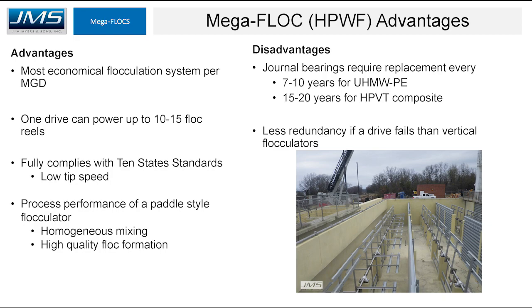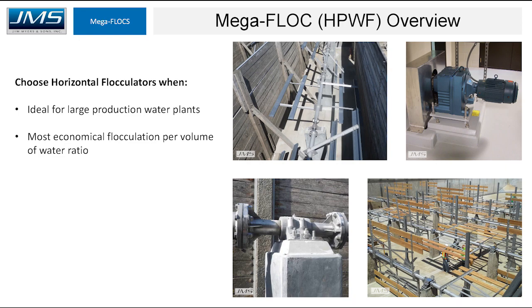Other advantages of the horizontal paddle wheel flocculator are that this is the most economical flocculation system per MGD of water. One drive can operate 10 to 15 reels as needed. It fully complies with Ten State Standards on tip speed, and the paddle style delivers the highest quality floc formation. Disadvantages are that journal bearings require replacement — with normal UHMWPE every 7 to 10 years, but with Teflon-impregnated composite material up to 15 to 20 years. With horizontal configuration there is less redundancy, so if a drive fails a large number of reels go out. Choose horizontal flocculators for large production water plants where economical flocculation per volume is the priority.